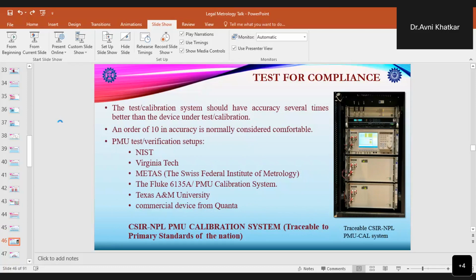is the Swiss Federal Institute of Metrology, the Fluke 6135A PMU calibration system, and there are some other facilities also, including those at Texas A&M University and a commercial device from Quanta. Of these setups, those at NIST and METAS are static systems. That is, they are fixed at their host locations to which devices must travel to be tested.